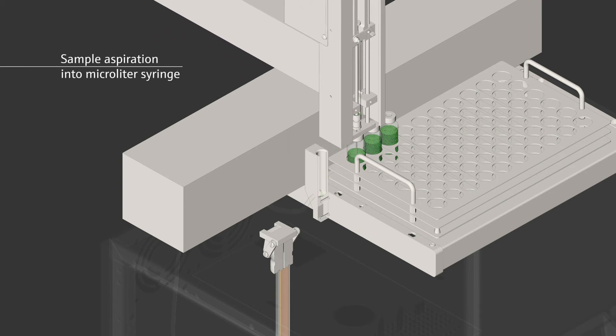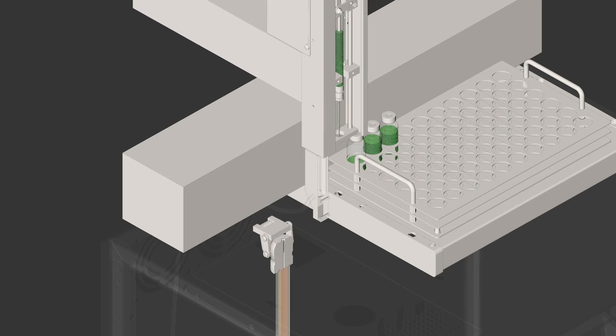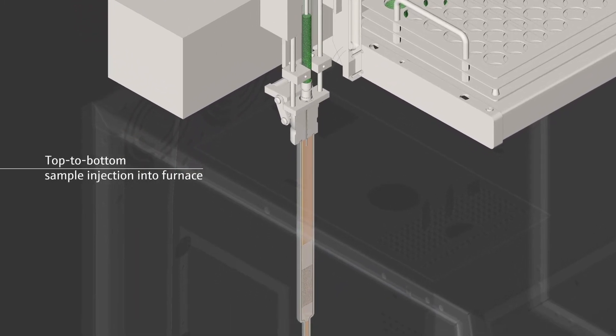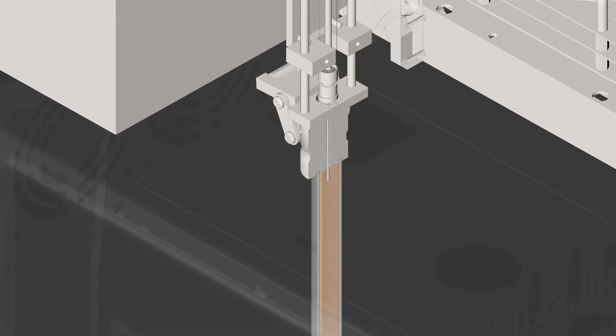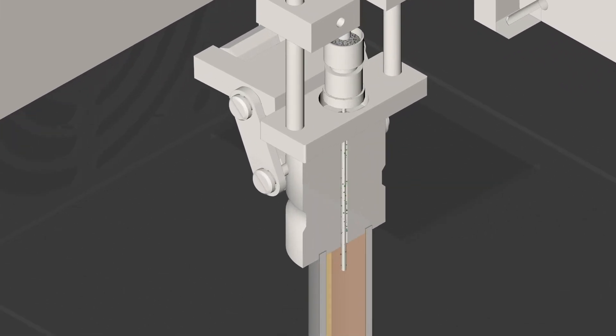The septum free direct injection is done top to bottom by a wide bore needle with complete particle transfer. No tubes and valves are needed. The injection needle is thermally cleaned in the furnace head during measurement.